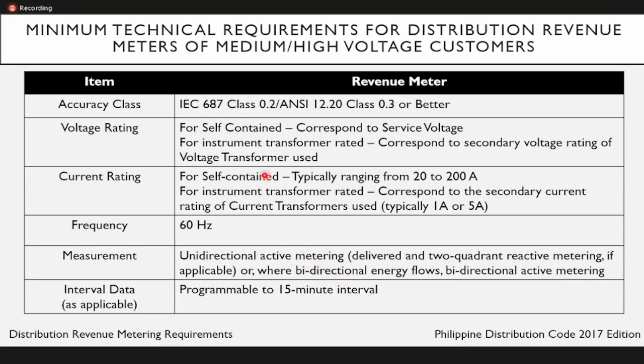For the meters of medium and high voltage customers, the accuracy class of the revenue meter will be based on IEC 687 class 0.2 or ANSI C12.20 class 0.3 or better. The voltage rating for the revenue meter for self-contained corresponds to service voltage. For the instrument transformer rated, it corresponds to the secondary voltage rating of the voltage transformer used.